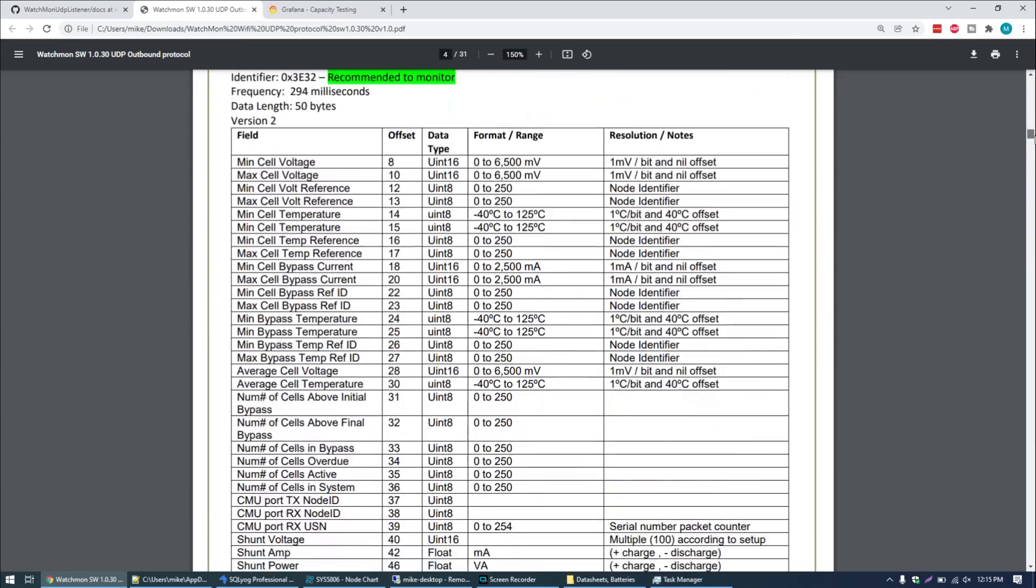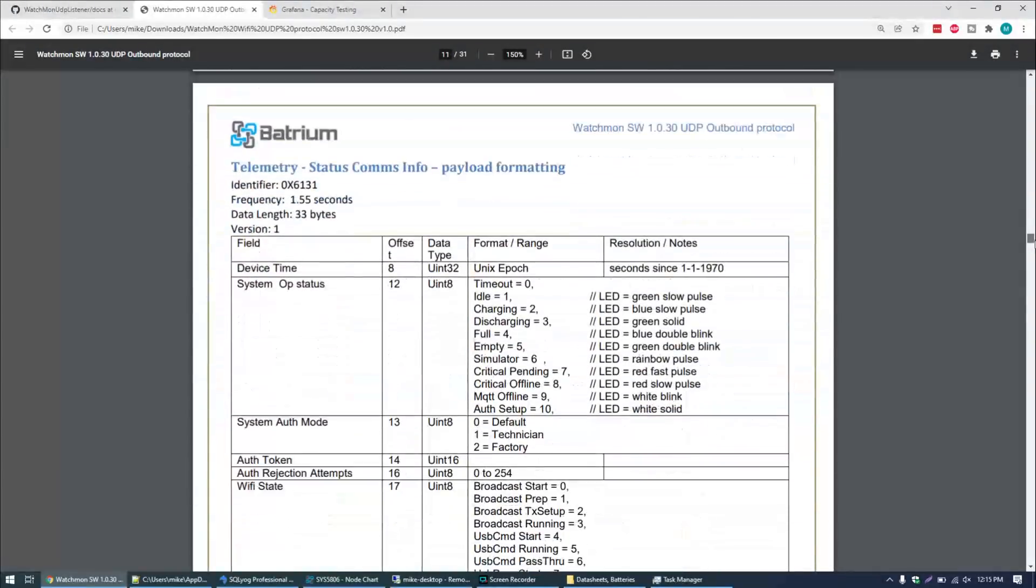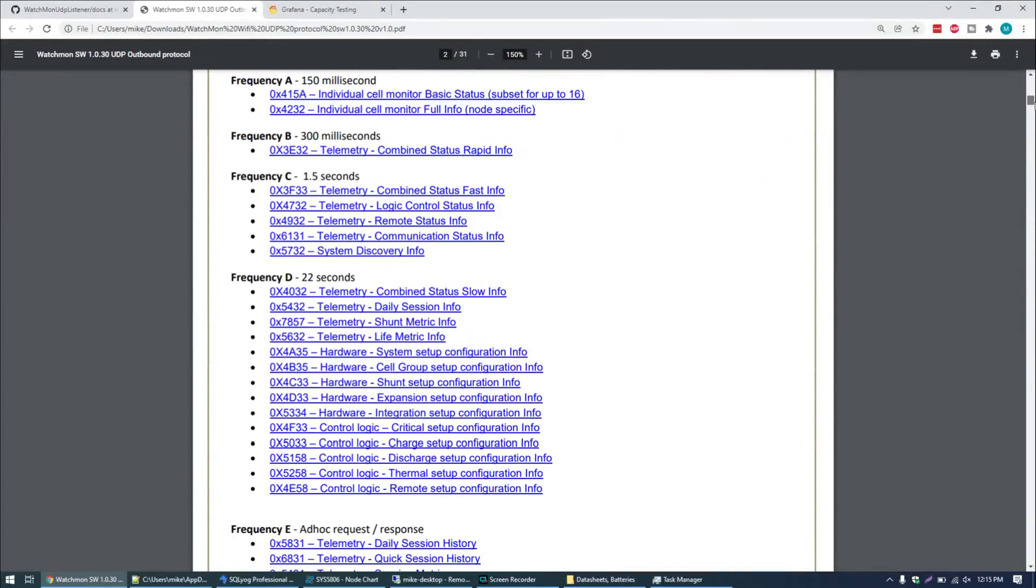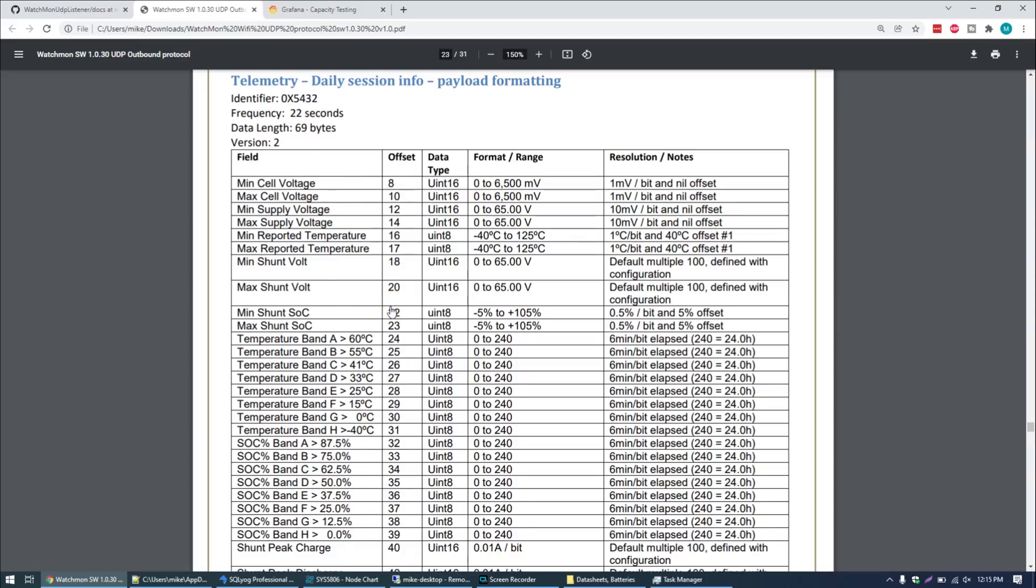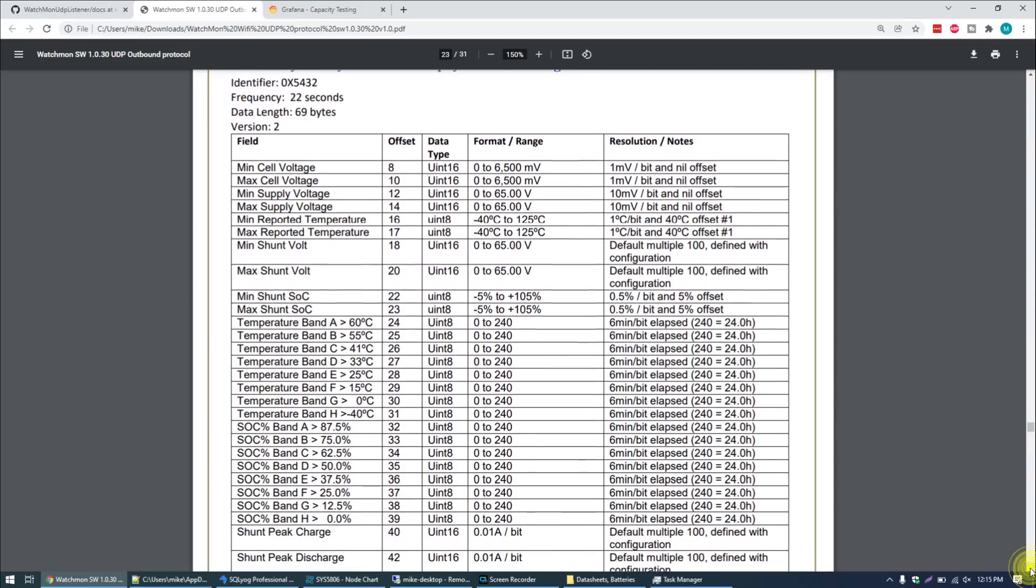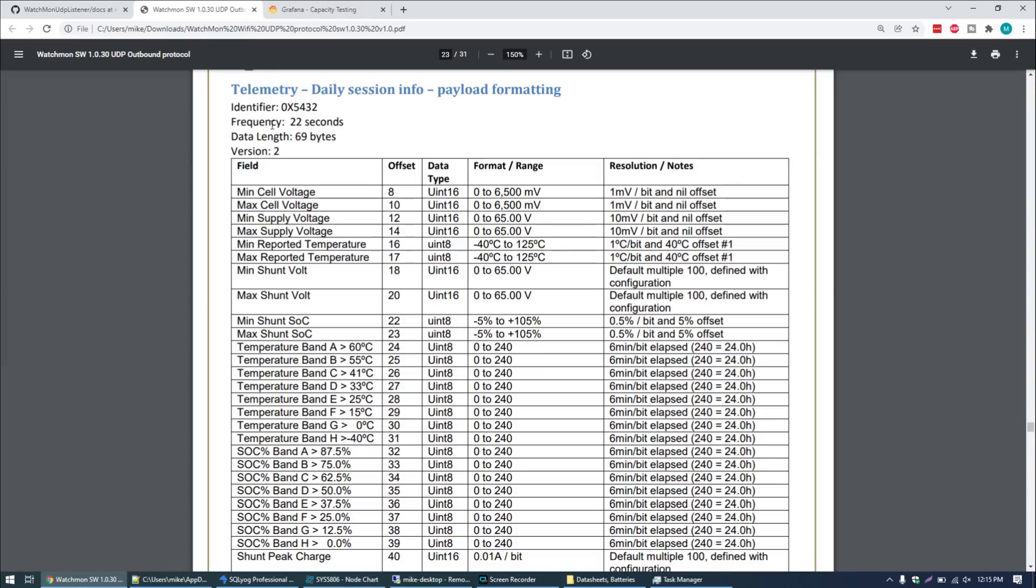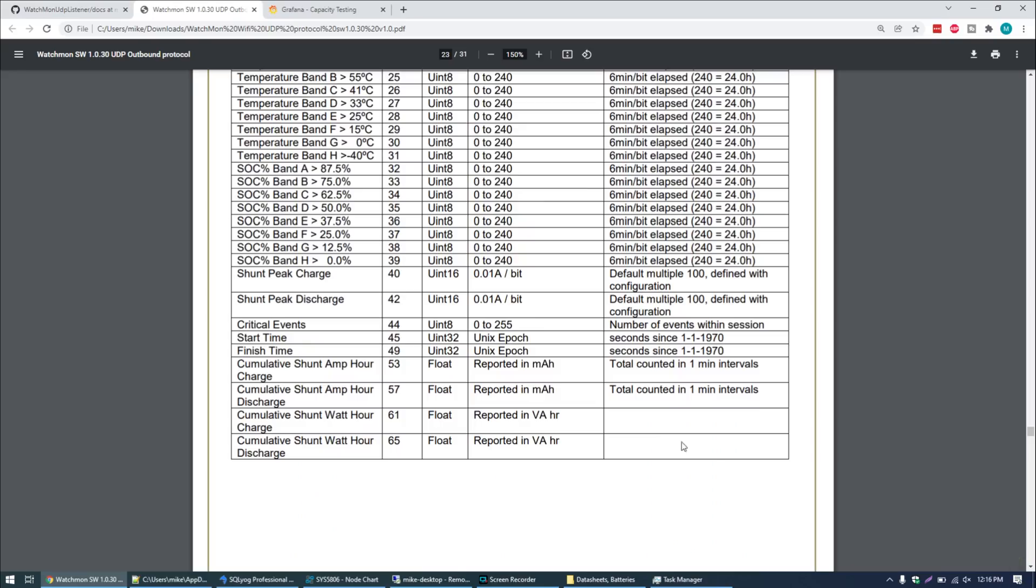As part of this UDP Listener there's a folder in here that says Docs and we have the entire protocol documentation for the Batrium BMS. You can see all the data fields. There are oodles of data fields here that this Batrium BMS will share across the network. The two that we care about are number 57 and 54. We see here is 0x5432. This is the daily session info and if we click on that this is where we're retrieving the amp hours and the watt hours from the shunt. We have cumulative shunt amp hour discharge and cumulative shunt watt hour discharged. This particular packet of information is broadcast every 22 seconds across the network. It reports that the discharged amp hours is counted at one minute intervals.